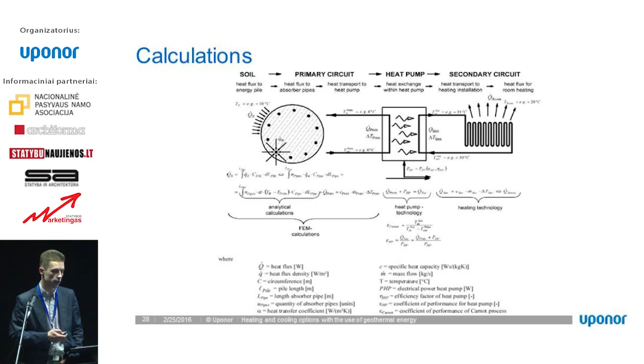When calculating how much energy we can get from the pile, for the heating mode, if the pile is less than 60 centimeters in diameter, it's around 40-60 watts per meter, or roughly 80 kilowatt hours annually. That's an example of what we can get from the pile for heating. For cooling, it's around 20-60.